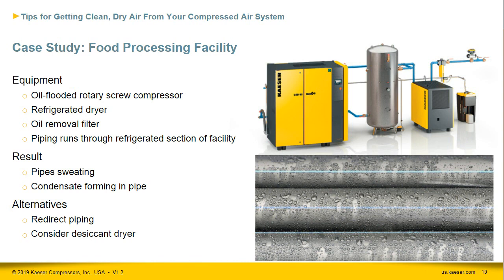There are lots of different ways to solve this particular problem, one of which was to redirect the pipe around the refrigerated section. Another consideration could be a desiccant dryer for just that section, but you have to consider the operating costs and the overall capital costs. Grayson's going to talk a little bit more about the pros and cons of that last option. Obviously, there are lots of different ways to solve this particular problem.